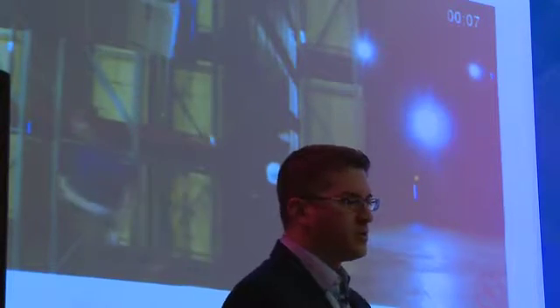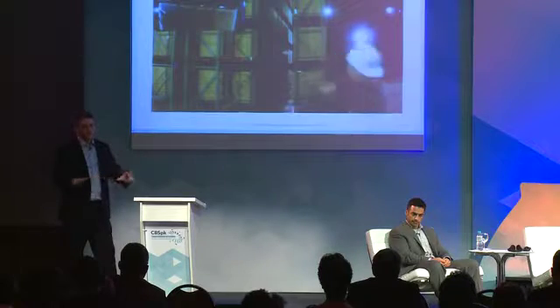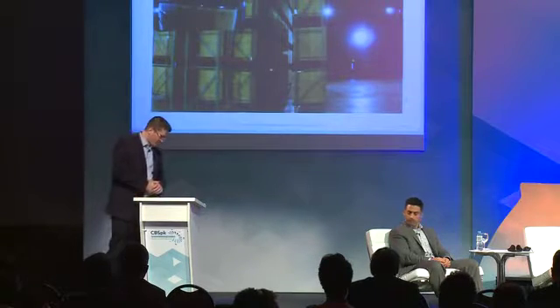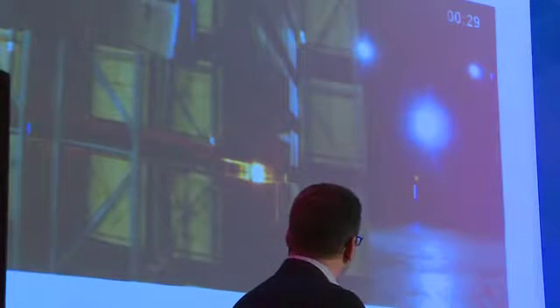So this is a test with carton commodity. We move the barrier from 6 meters up to 9 meters. Same exact sprinkler layout. And the commodity in this one is cartoned unexpanded plastics. So it's plastic cups, hard plastic cups, polystyrene, but hard plastic cups, stacked inside cardboard boxes. This one's ignited inside the transverse flue.